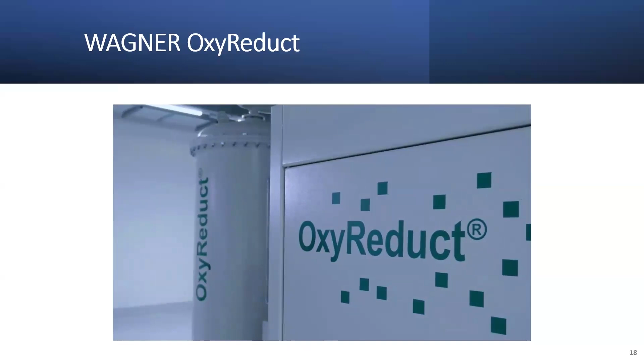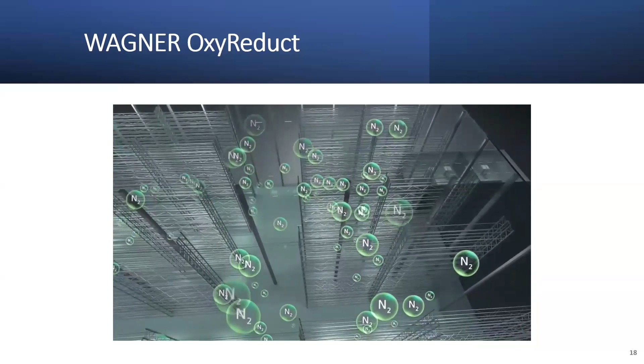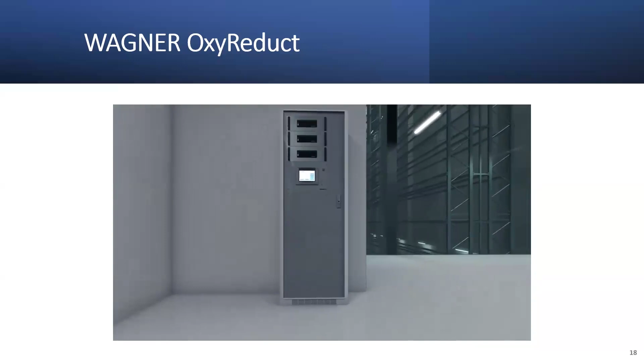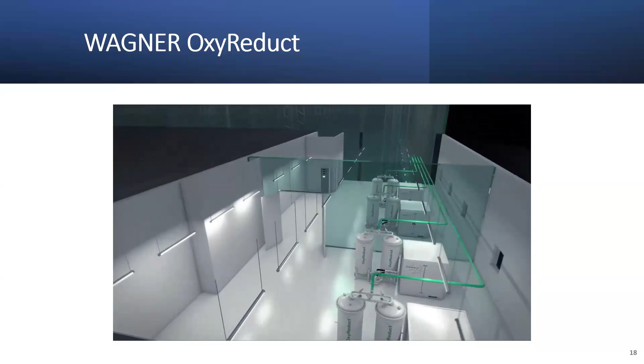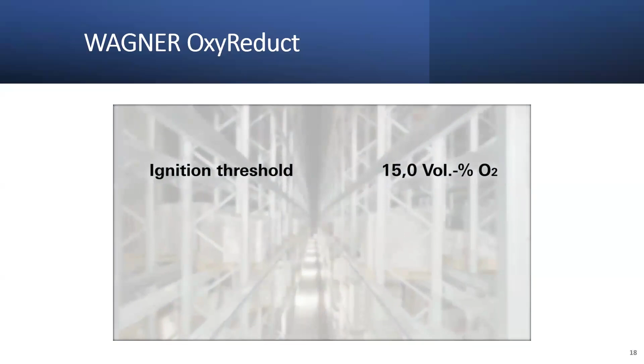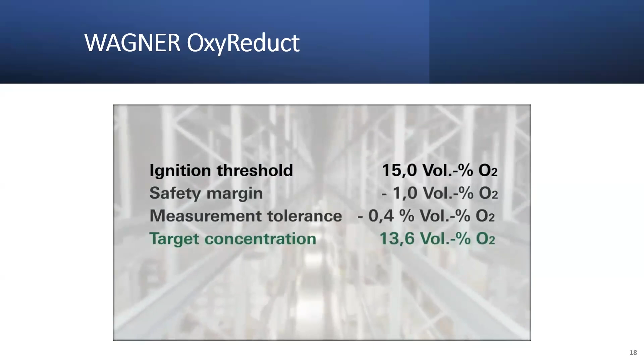OxyReduct: the idea behind action rather than reaction. The active fire prevention system minimizes the risk of fire from the outset. Fire needs fuel, heat energy, and sufficient oxygen at the same time. The system's principle is based on lowering the air's oxygen concentration in the warehouse through controlled introduction of nitrogen. This puts the protection level below the ignition threshold of the prevalent materials. Sensors and the OxyControl control system monitor the oxygen level in the protected area to ensure that the oxygen concentration is continuously maintained at the specified level. The nitrogen will be produced on site and on demand and is introduced into the protected area by pipes. The inert gas nitrogen can be distributed homogeneously and displaces the oxygen present in the room air. For cardboard boxes, the ignition threshold is 15% oxygen volume. With the safety margin and measurement tolerance, the target concentration in the high bay warehouse is therefore 13.6% volume.